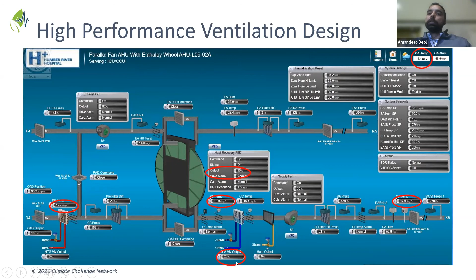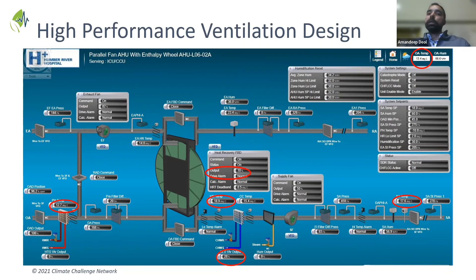And that's done through the cooling coil operations, where the thermal wheel is run at a higher speed, which increases the supply temperature. Then the cooling coil is used to recover that heat, which is brought back through the heat recovery chiller and put back into the system through a heating loop, which again offsets the natural gas. So that's an approach. Maximizing the use of the heat wheel is being followed in this facility, which has led to a substantial reduction in natural gas usage.